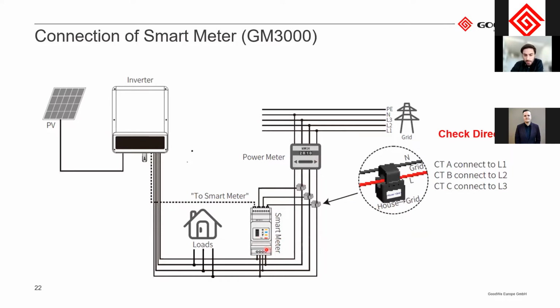On the bottom side here, you need to connect the voltage sense, and here it's also important that you connect the voltage sense as close as possible to the current transformers so that there are no loads in between. The loads should be here, and then the voltage sense and the CTs should all be connected just before the grid connection point. This is important because if you connect some loads here, then the reading of the voltage here and the current here will be wrong. So please make sure that there are no loads in between here.